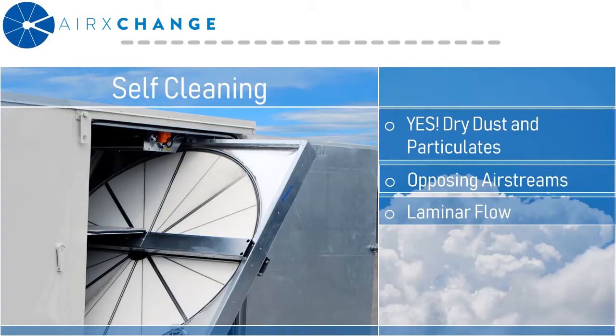And that's because the wheel is rotating between two opposing airstreams and it's constantly exposed to high velocities blowing in either direction, coupled with the fact that the airflow is laminar in nature and not turbulent like a coil. A quick fun fact for you is that most wheels have a 70% open face area, meaning if the particulate is small enough, it will be blown directly through the media, and if it's large enough, it will get sucked to the face and blown off when it enters the opposite airstream.